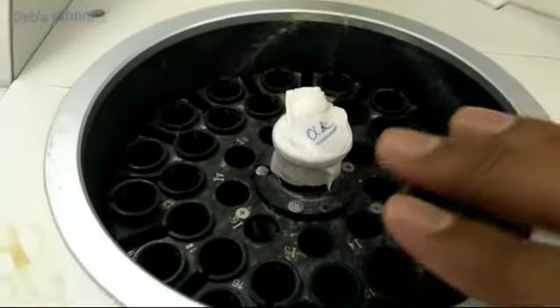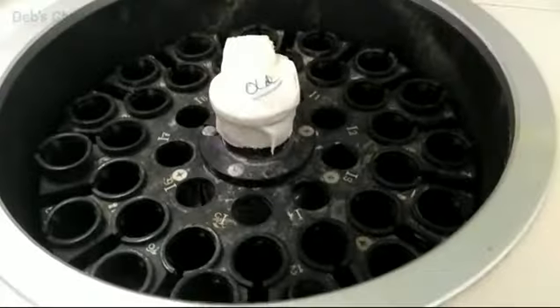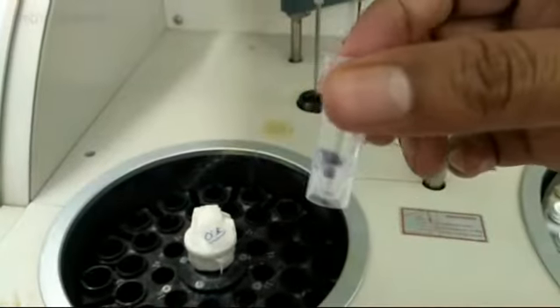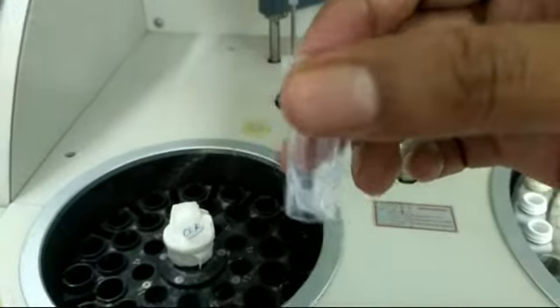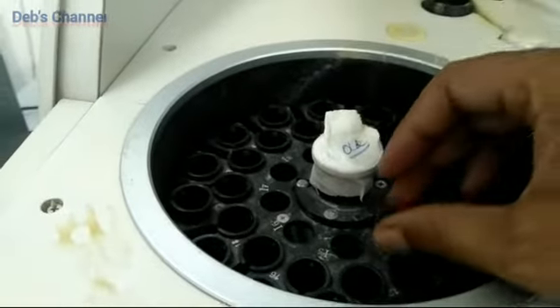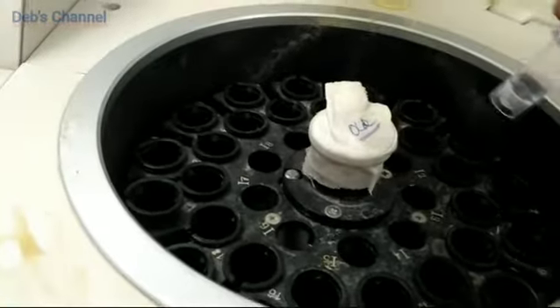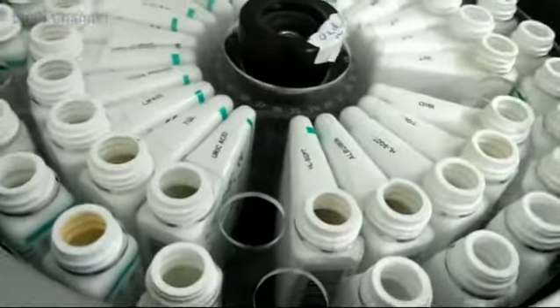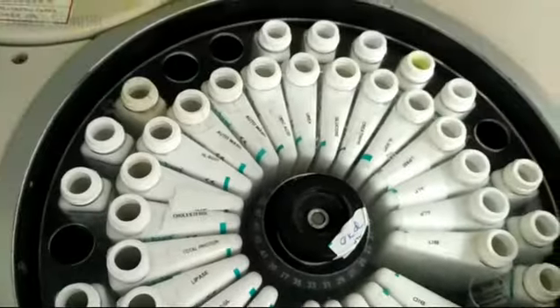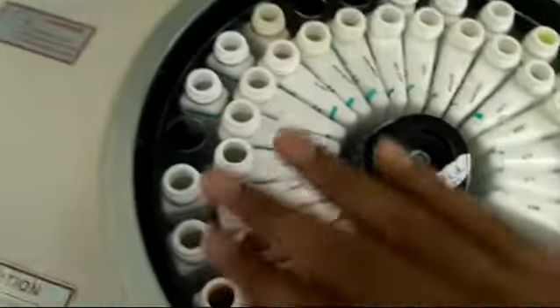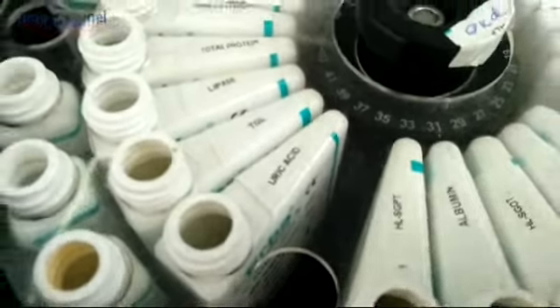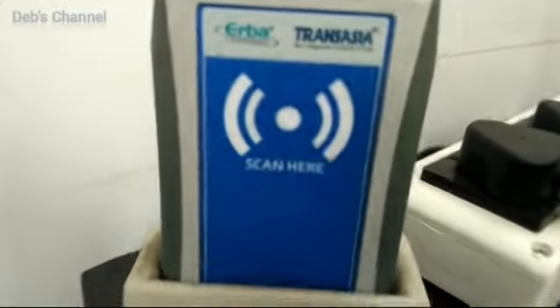This is the sample receiving unit, and we have to put the sample with the help of this sample cup. We have to add a sufficient 200 or 300 microliters of the sample, and then put the sample cup in the appropriate position and program according to the position. And this is the reagent cup, and the reagent should be scanned, and then put in the reagent cup. The machine will take the reagent automatically, and this is the scanner to scan or program the reagent with the machine.